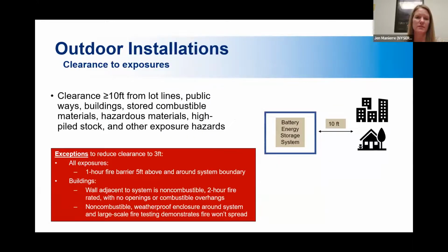I mentioned outdoor installations have some different requirements from indoor installations. And I think someone might have been asking about this. I know we've asked about it a lot. What can they be near? What should they not be near? Any outdoor installations should have at least 10 feet of clearance from any lot lines, public ways, buildings, combustibles, things that can catch fire, basically any other hazards needs to be at least 10 feet away.